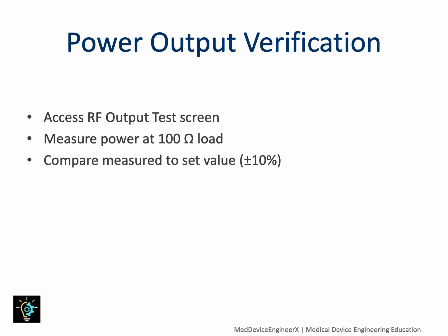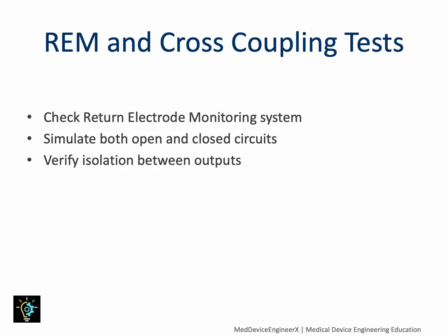This test confirms that the generator's actual output matches its displayed setting. In service mode, open the RF output test screen, apply the 100 ohm load, and record power at several output levels, typically 30, 100, and 300 watts. The measured values should remain within 10% of the set point. Deviations may indicate calibration drift or internal board faults. Accurate power output is essential for predictable surgical performance.